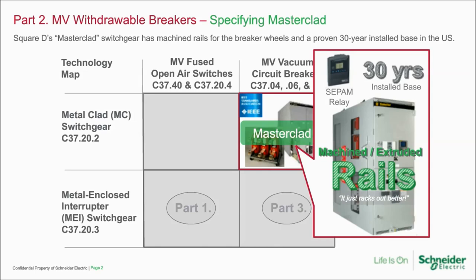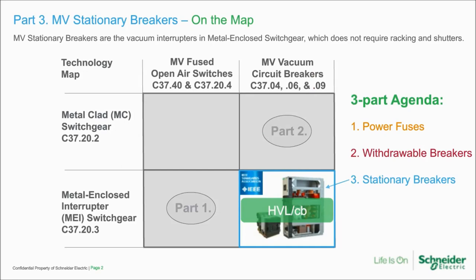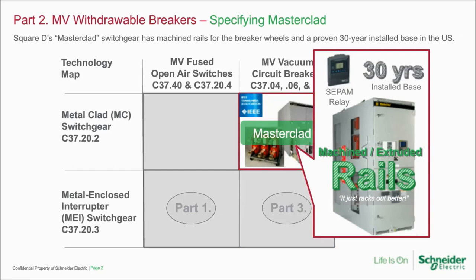Wendell, that's the end of part two. Do you have any questions on Masterclad? Yes, there are a number of questions. From the HVL conversation: do the live line indicators require PTs? No. The live line indicators are actually an electronic version of the old mechanical system called FuseLogic, which told you that one of the fuses was burned out. In this case, we have a special capacitor that indicates directly that the line is hot or not — no need for a PT.